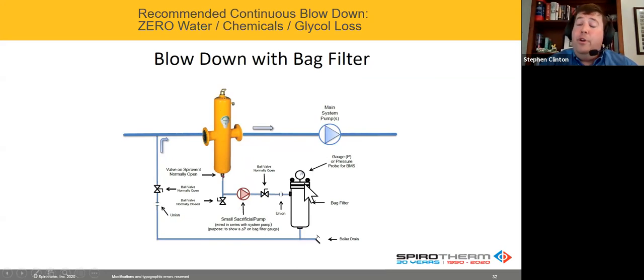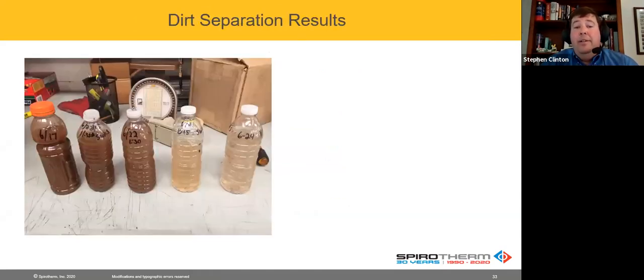The nice thing too, for you owners out there that may be participating with us, is you can see a DP, so you don't have to change it until your pressure drop gets higher. Also, if a project has just come online and it was supposedly flushed and cleaned, and all of a sudden you get a bunch of junk in the system, you can hold that and have a meeting with your friendly neighborhood contractor and say, hey, can you help us here? Because here's what we've just now picked up in the system. So definitely recommend some type of a system like this.